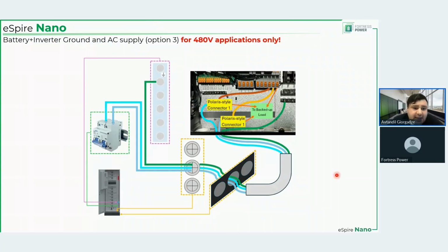Let's say you have neither smart ports nor load ports vacant. All of them are occupied by whatever is connected to them, right? Then what you do is you either take it from the panel that you are backing up, and we want the backed up power to be delivered to the battery because we want those AC circuits like HVAC and everything else to work even if the grid went down. So you either go and take that AC supply from the facility itself, from the backed up load panel, or, arguably an easier way, you introduce 2 Polaris connectors.